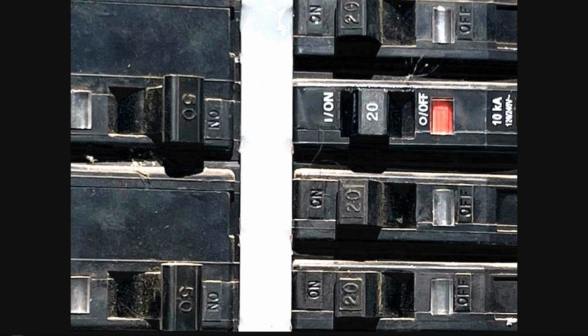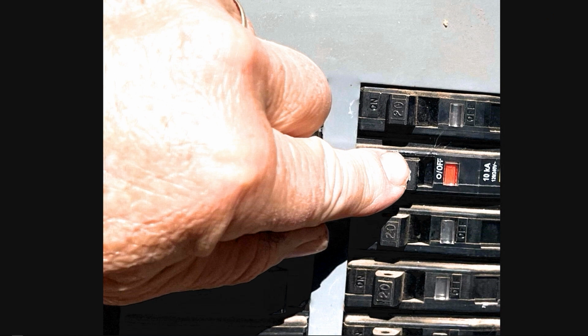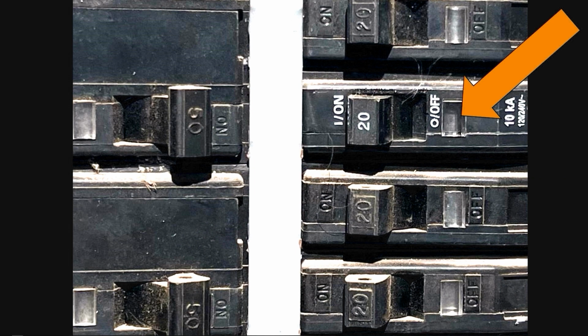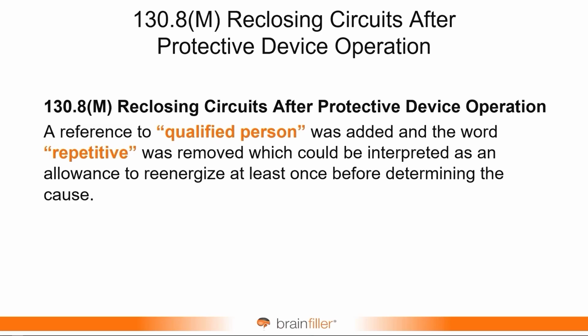Let's say the power goes out. What do you do? Well, you try to determine why the power went out. Did a protective device trip? What do you do if the protective device trips? Most are going to say reset it. And there you go. NFPA 70E has a different view of this. It's referred to as reclosing circuits after protective device operation.